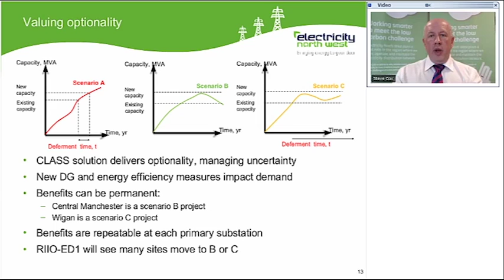At the far right-hand side, we see some other groups, and our Wigan BSP group is an example of that, where the demand oscillates close to or slightly above the existing capacity limit. And again, we intend to use CLASS to control the peak demand in that group, to keep it within capacity limits so that we don't need to invest. And the key thing, I think, under the CLASS project, when we show how the technology works and how it can be applied, is that it can be applied at every substation in the network and has an enduring benefit. And we certainly believe in our load modelling that scenario A will probably not be typical of the future, and we'll see more of the electricity network behaving as B and C as customers change their use, install generation, as DNOs buy DSR, and we have a much more active market and therefore a much more volatile demand.